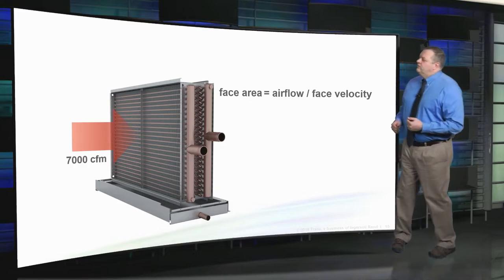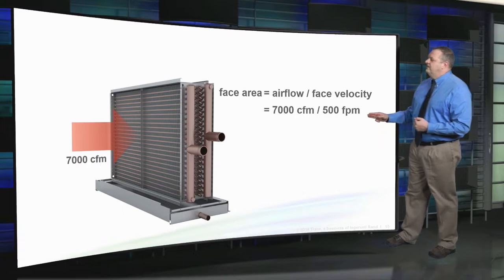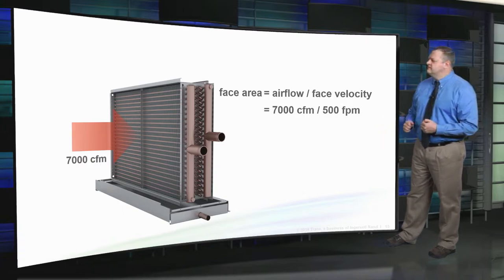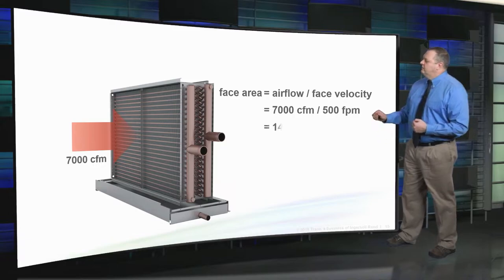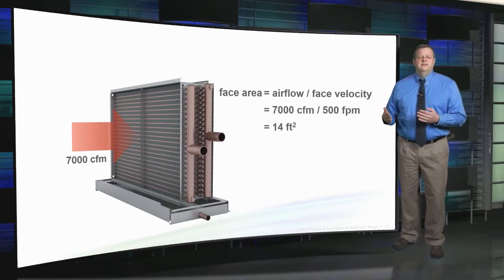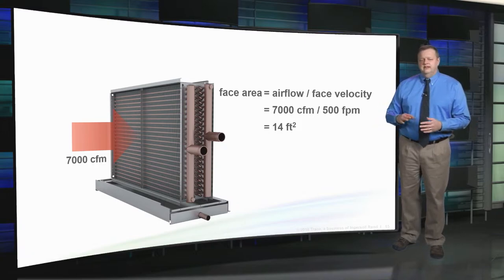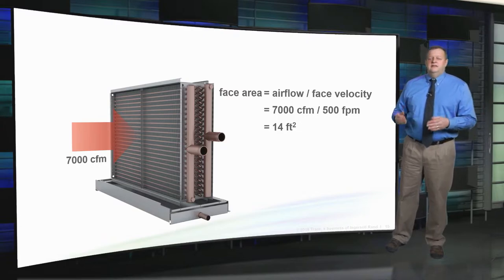The entering chilled water temperature is 42 degrees with a 15 degree delta T at design conditions. To select the size of this coil, let's start with a traditional sizing convention of 500 feet per minute face velocity. Dividing the airflow of 7000 CFM by 500 feet per minute results in a coil face area of 14 square feet. We'll select the size 14 air handler, since the unit size typically represents the nominal face area of the cooling coil.